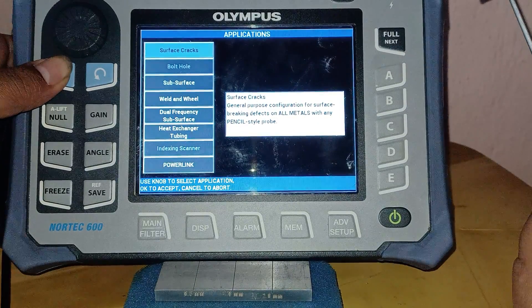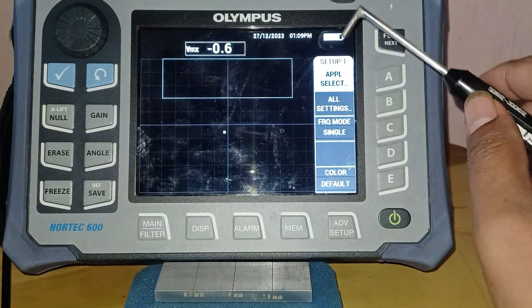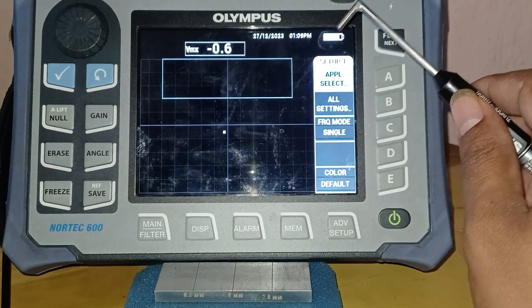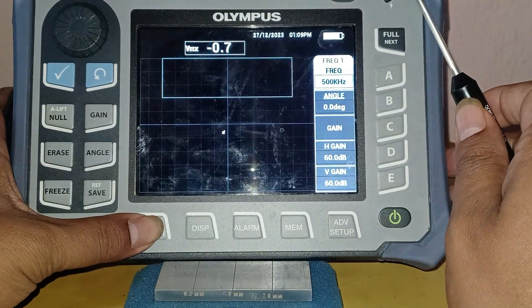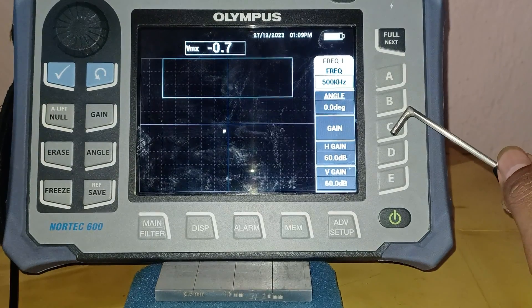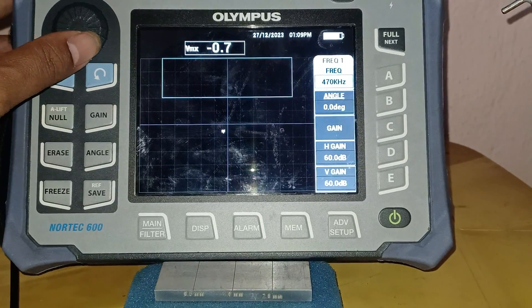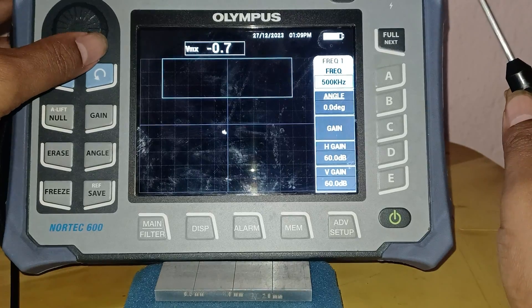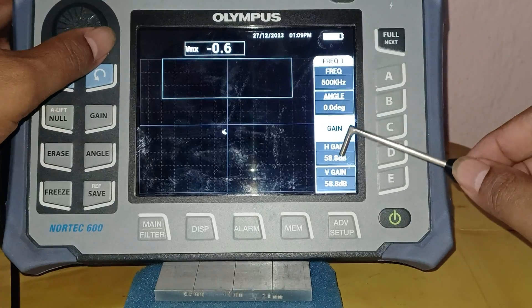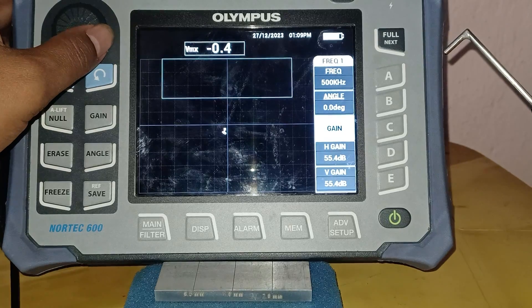I am pressing the right button and entering the impedance plane settings. This is the impedance plane of a normal eddy current testing setup. Going to the main menu: the frequency I have chosen is 500 kilohertz, and the horizontal gain is 60 and vertical gain is 60. I am reducing the gain slightly — pressing the gain button. If I reduce the gain, both channels reduce equally. I am keeping the gain at 55 dB.